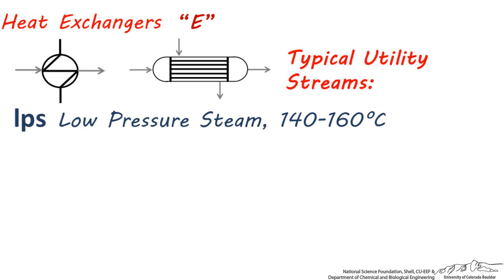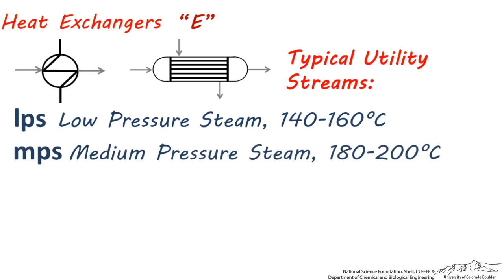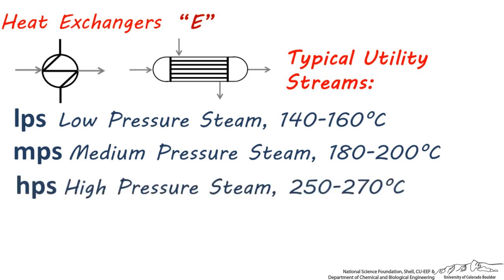Low pressure steam, abbreviated LPS, which is saturated steam around 140 to 160 degrees centigrade going into the heat exchanger. Medium pressure steam, abbreviated MPS, which is saturated steam around 180 to 200 degrees centigrade going into the heat exchanger. High pressure steam, abbreviated HPS, which is saturated steam around 250 to 270 degrees centigrade going into the heat exchanger.